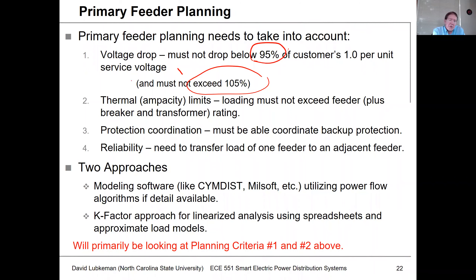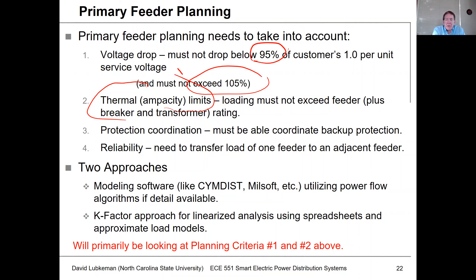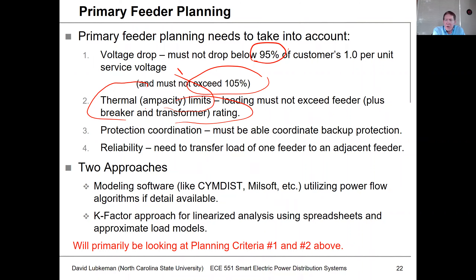You're also concerned about not exceeding thermal and ampacity limits for pieces of equipment. At the top of the feeder, you're looking at circuit breaker currents and top feeder line segment loadings. Also, you're looking to make sure you're not overloading transformers on the circuit. You need to make sure that you can coordinate various protection devices, with fault current levels within certain ranges where you can coordinate protection.